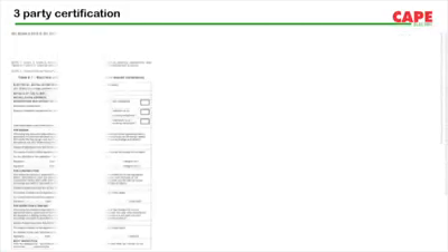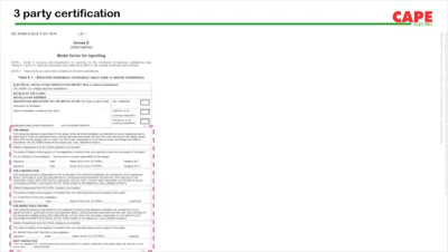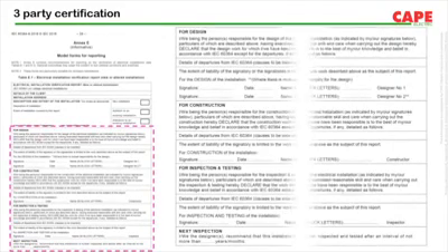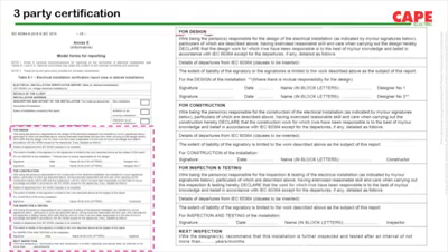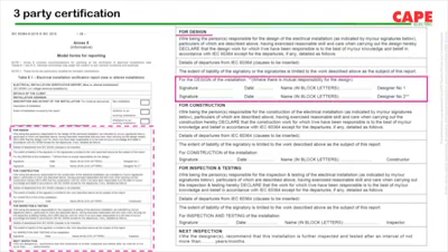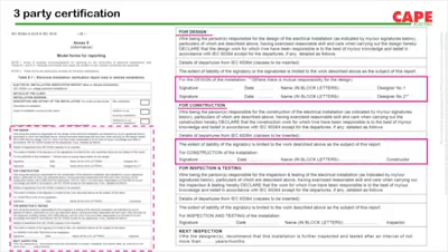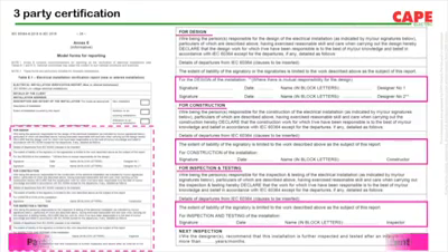IS 732 also provides the format for testing and inspection. If this format is followed all over India, it's easy for an expert to find out the mistakes in an installation. The format which I am showing is from IEC 60364 Part 6. There you can find a statement from the designer, contractor, and the inspector. As a result of this certification, parties involved can be held responsible in case of an accident in a building.